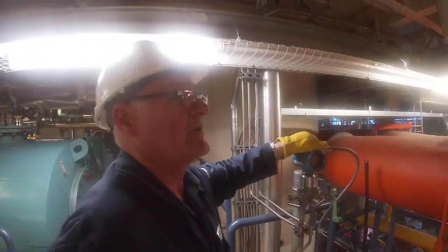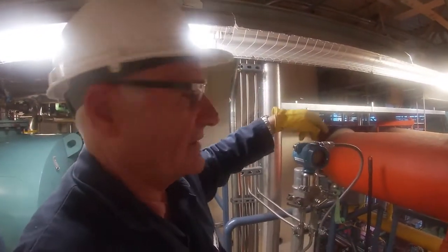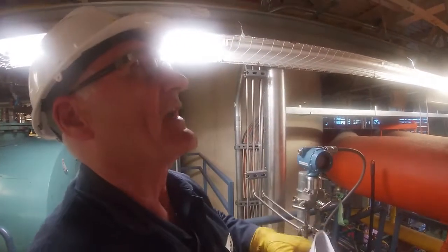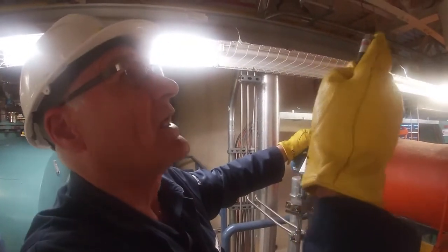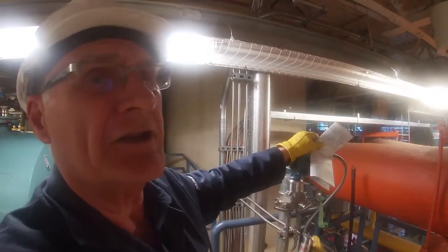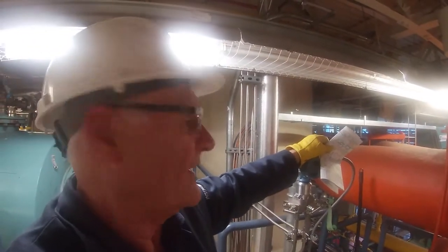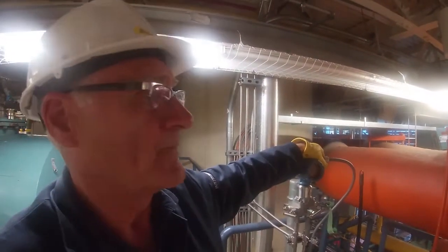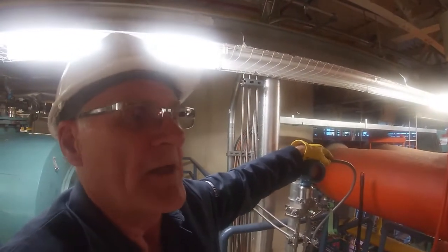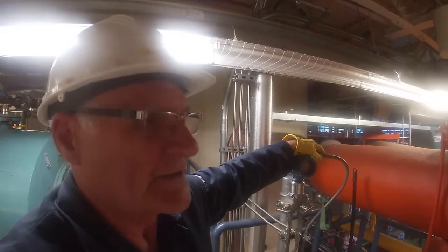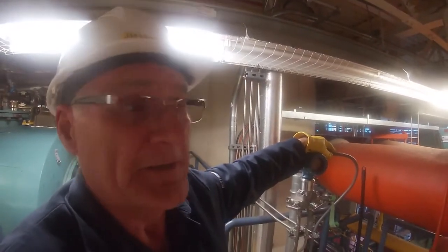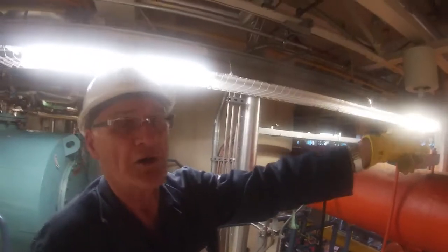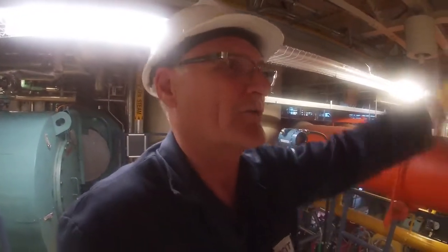It's a multi-variable transmitter which actually looks at the differential, and then it knows what type of orifice plate you got in there and exactly what the flow should be. And this is actually running a 4 to 20 milliamp signal. Our airflow transmitters are the same. They're smart multi-variable transmitters. Okay, we're going to go to the boiler next, so we got to go back down and cross up to the boiler.